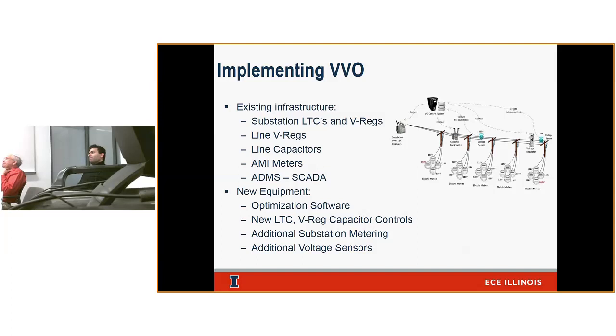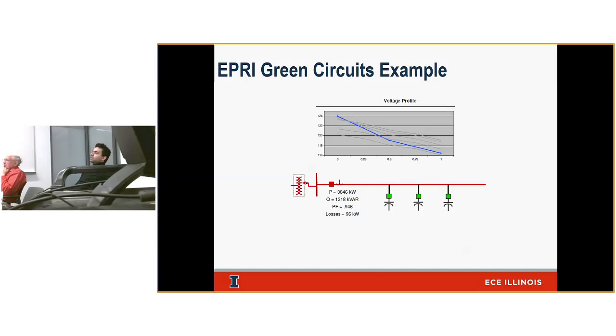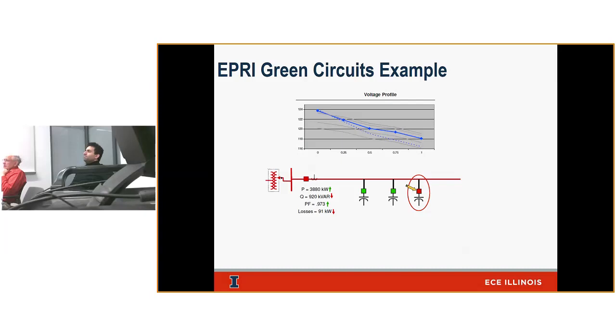Let's look at an actual circuit with actual data. Here's a circuit with an LTC — a load tap changer — and three capacitor banks along the feeder. The measurements before doing anything to the capacitors or voltage regulator are listed: P is real power in KW, Q is the VAR component, power factor in real time, and calculated losses. The voltage optimization algorithm typically tries to use cap banks first to flatten the voltage profile. The losses here are calculated based on a real-time load flow.